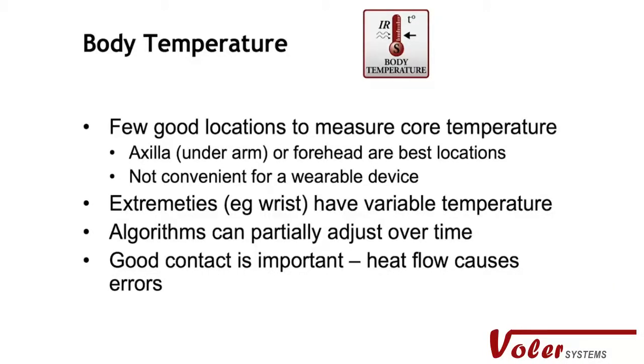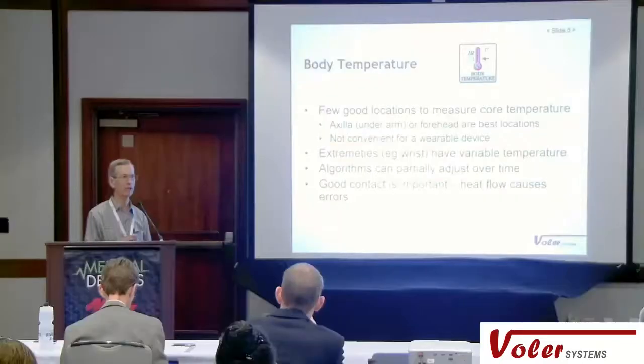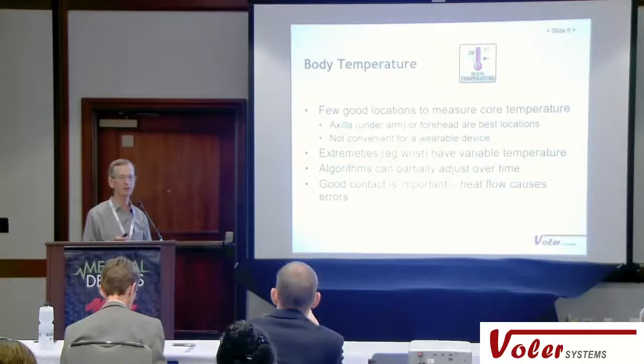Another important thing about measuring temperature is contact. You're actually measuring heat flow from inside the body to outside. If the sensor doesn't make good contact, you're not going to measure the temperature you wanted. For example, on the wrist, I wear my watch rather loose — it may not make good contact. So how people actually use the device becomes very important.